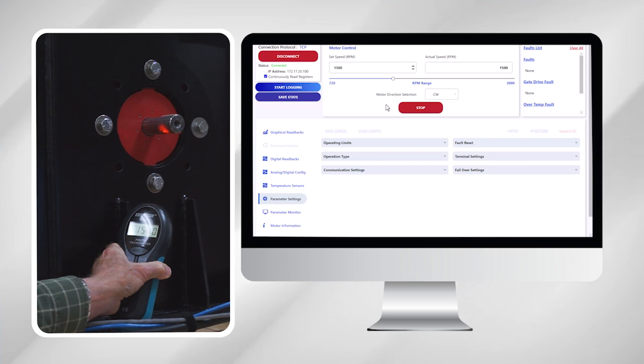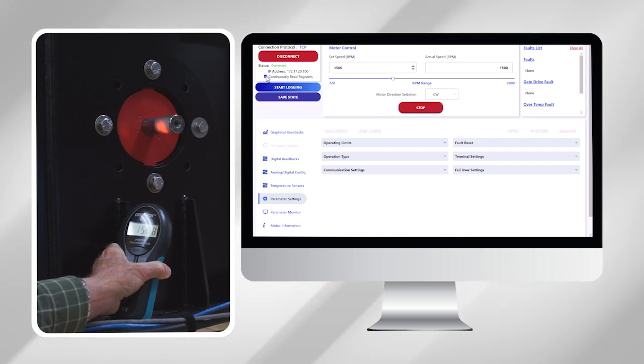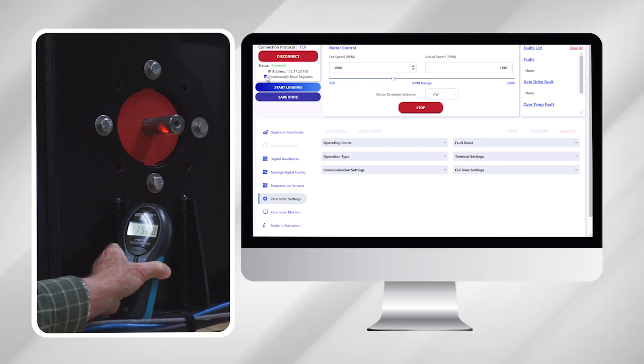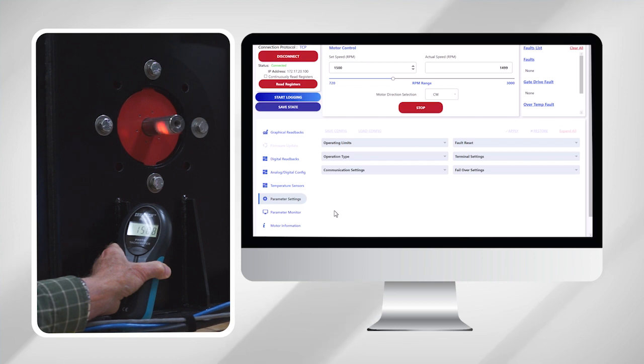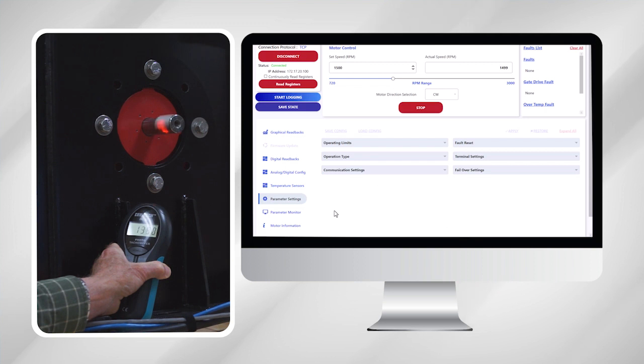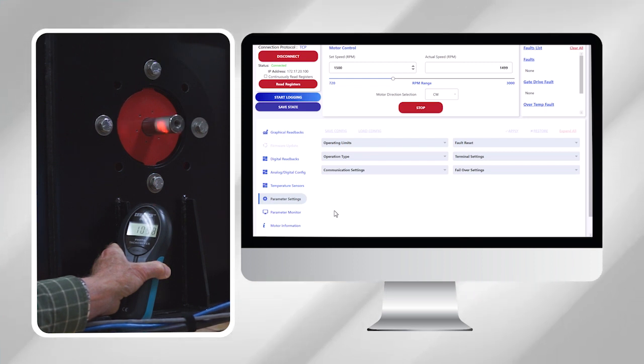I'm going to break connection between the laptop and the motor by clicking this button in the upper left hand corner. Once I click it, it'll stop talking to the motor and we should enter failover mode in about five seconds. So I'm going to click this button and you can hear the motor slowing down. If you remember the setting for failover was 1000 RPM. So it should level off at 1000 and you can see the tachometer is indicating that.